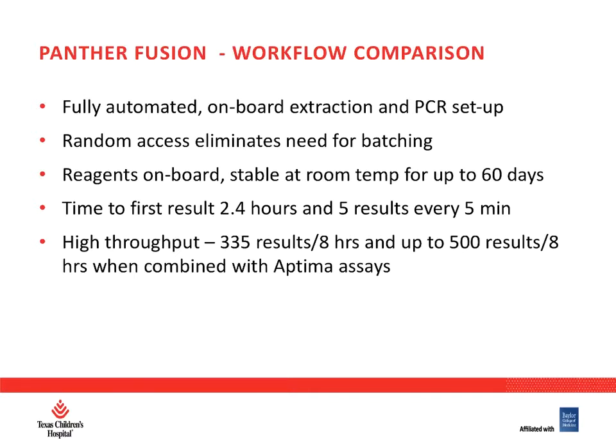So we can slide samples in throughout the day if we need to. We don't have to batch them all in one run. And they also have reagents on board that are stable for up to 60 days on the instrument. And the results are fairly timely, particularly since we're trying to do a broad number of respiratory viruses here.